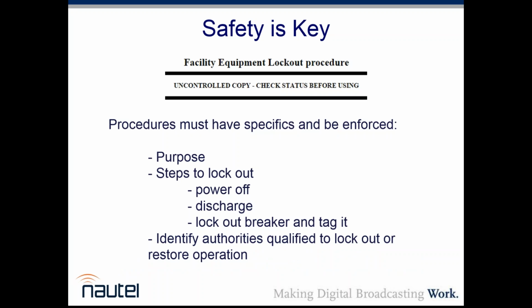Effectively, the way it works is that the primary disconnect for the transmitter has a key in it. Until the disconnect is in the off position, you can't close the locking bar to remove that key. That key goes into the transmitter and will allow access to a second key, which can't be removed until the antenna ground switch in the transmitter is closed to ground the antenna connection, at which point you can get the second key, which lets you open up the lockbox that accesses all the cabinet keys.